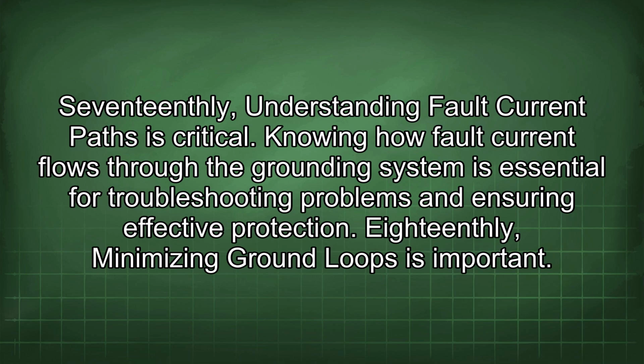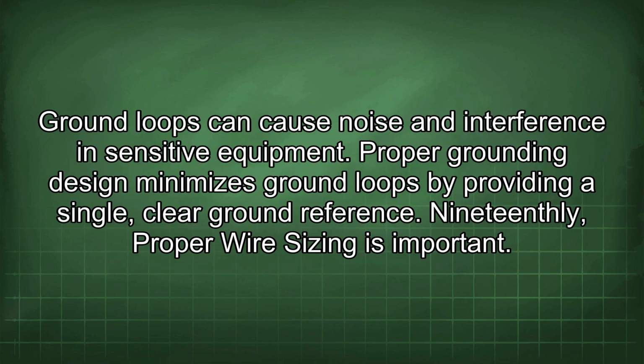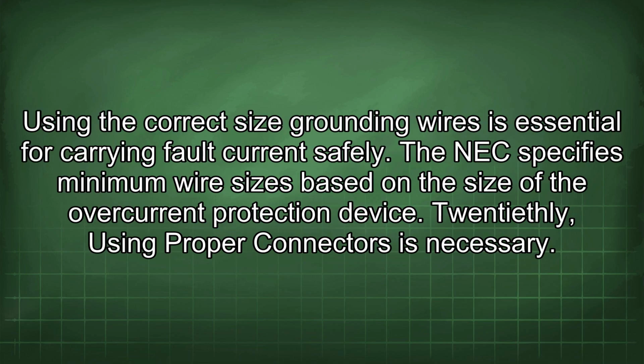Eighteenthly, minimizing ground loops is important. Ground loops can cause noise and interference in sensitive equipment. Proper grounding design minimizes ground loops by providing a single, clear ground reference. Nineteenthly, proper wire sizing is important. Using the correct size grounding wires is essential for carrying fault current safely. The NEC specifies minimum wire sizes based on the size of the overcurrent protection device.